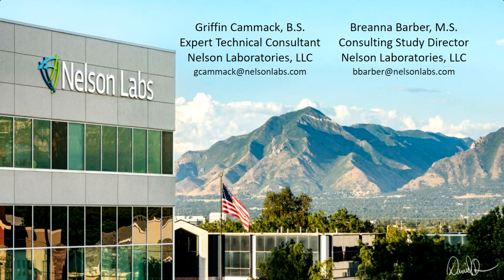Okay. The next question we have, how do you perform point-of-use cleaning if the device is used on the body continuously, i.e. 24/7? What is the recommended cleaning frequency? Yeah, so there is no guidance on how to determine what is the recommended cleaning frequency for those sorts of devices. Typically we see either two recommendations: to clean it daily, or to clean it as visible contamination is seen.